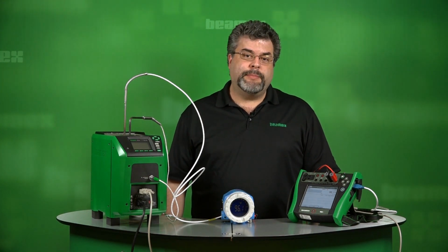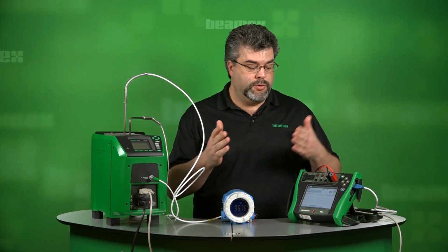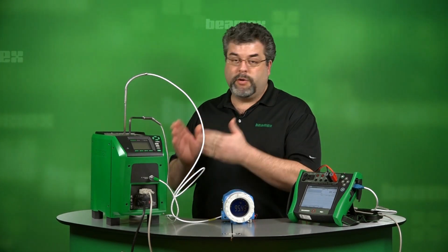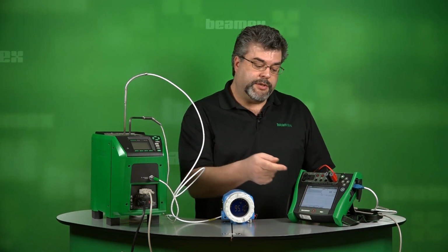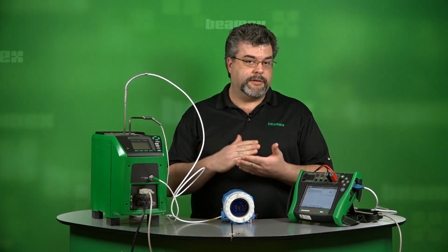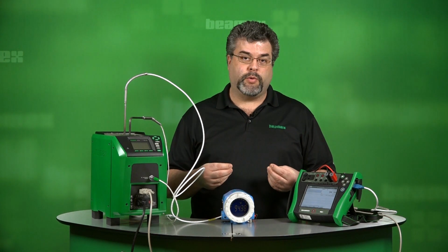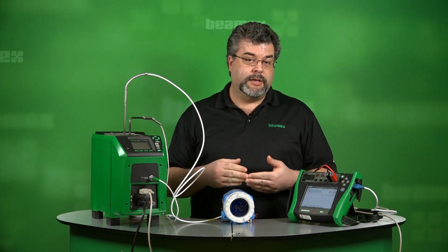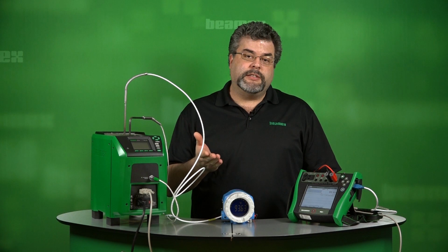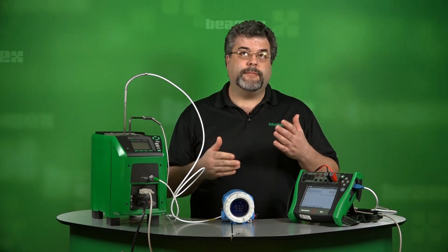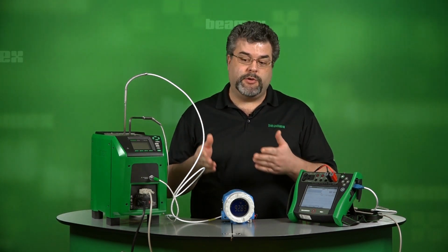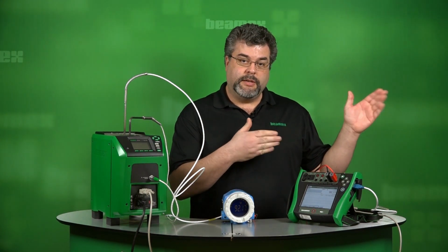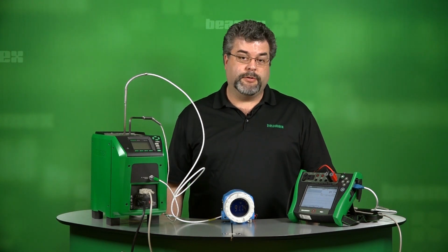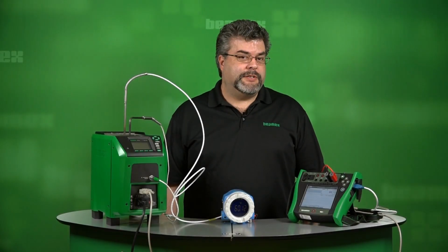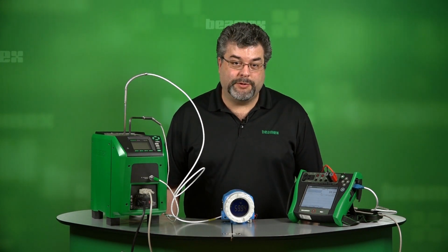So what you've seen is an automatic calibration of a temperature loop using an MC6 and an FB150. All we did was press the start button and it ran through all of our temperature ranges, grabbed all of the test points, did the calculations. Now during that time, you could have done something else. You could have maybe installed the last temperature element that you just tested, or maybe went out to grab the next one on your list. But either way, this calibrates whether you're here or not. So now you've seen how to do an automatic calibration of a temperature loop.